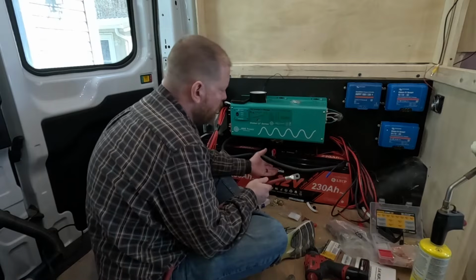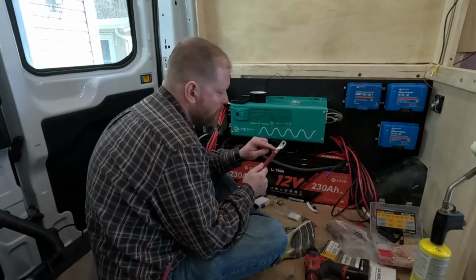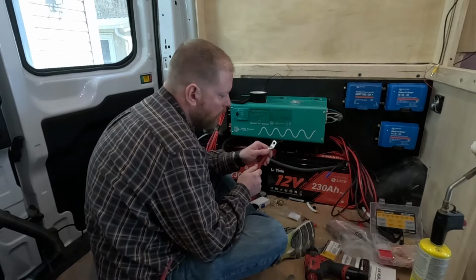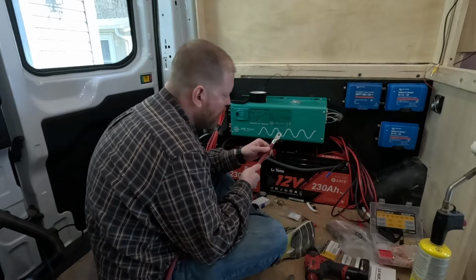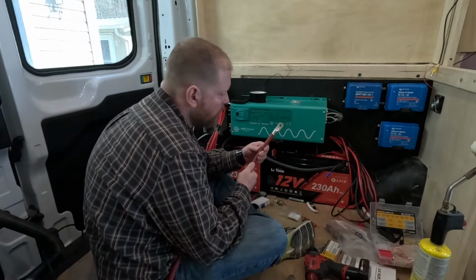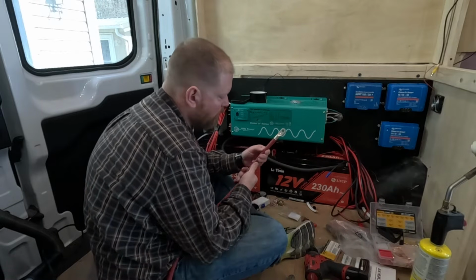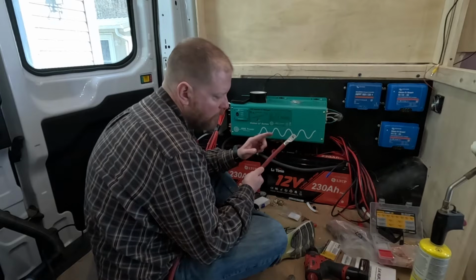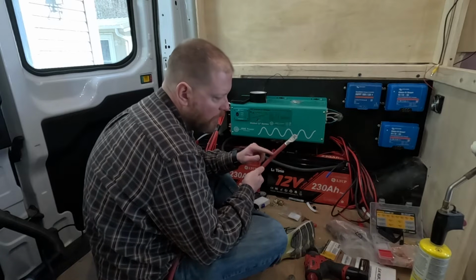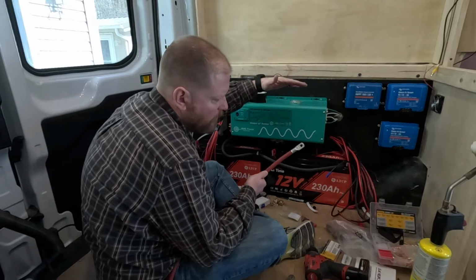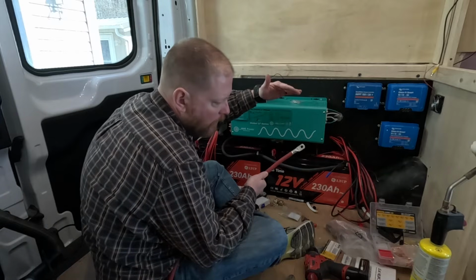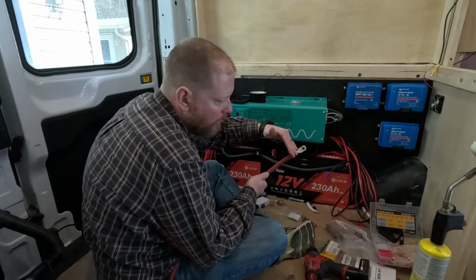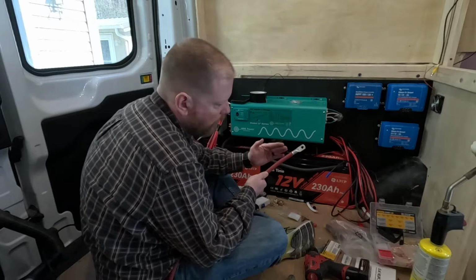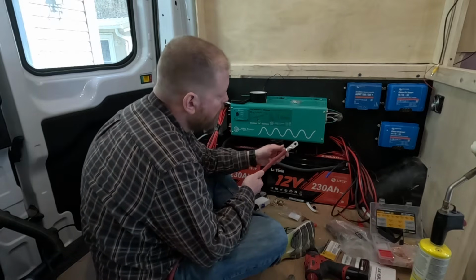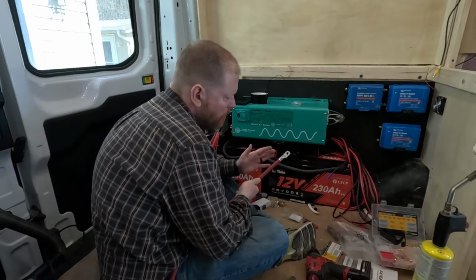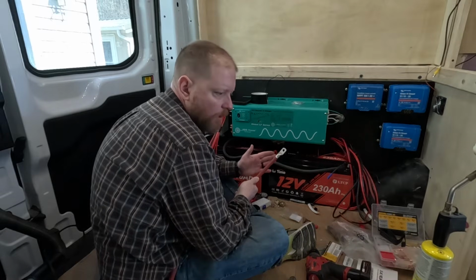Alright, I'm working on making the battery cables now. I'm using these tinned copper lugs, they're 3/8. I'm using 2/0 cable. There's a difference between 2 gauge and 2/0. Basically, it starts at like 18, 20 gauge, and the lower the number, the bigger the cable, and then it starts working its way back up once you get to 0. So I'm right on the border of 2/0 and 4/0 cable.